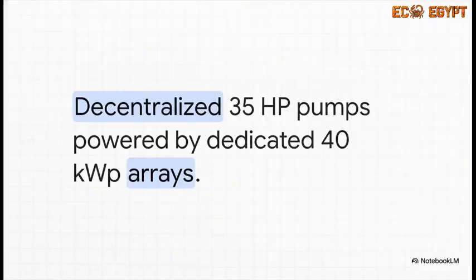So we're shifting our focus now from industrial microgrids to crucial agricultural applications. Instead of relying on one massive pump, which, let's face it, is a huge single point of failure, the engineering choice here is pretty brilliant. We have 125 horsepower total load, but it's divided across 4 independent stations. For just one of these stations, a 35 horsepower pump is fueled by a dedicated 40 kilowatt peak PV array. That's specifically 72 Jinko 535 watt peak modules per station. This setup ensures that every single well operates autonomously, which drastically increases the farm's overall water supply reliability.